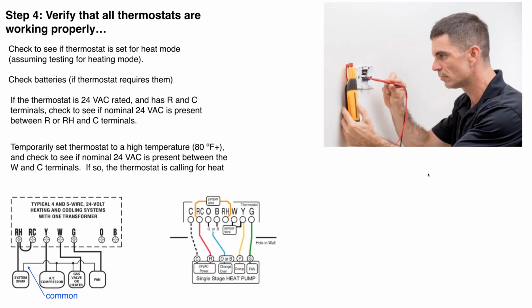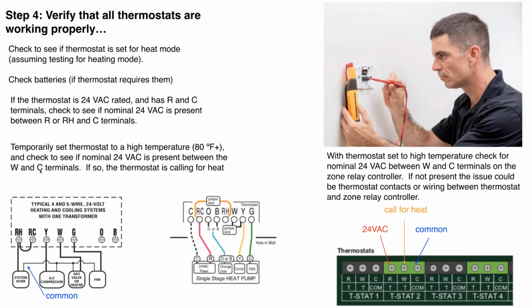You can check operation of the thermostat, temporarily set it to a high setting, higher than what the room temperature is by several degrees. Say you turn it up to 80 degrees and check to see, do you have 24 volts nominally between the W and the C terminals, okay? We want to make sure that the thermostat is at least giving the electrical contact closure that is a call for heat, all right? And down on the zone relay controller, you can also check down here, basically 24 volts between R and W, between W and C.